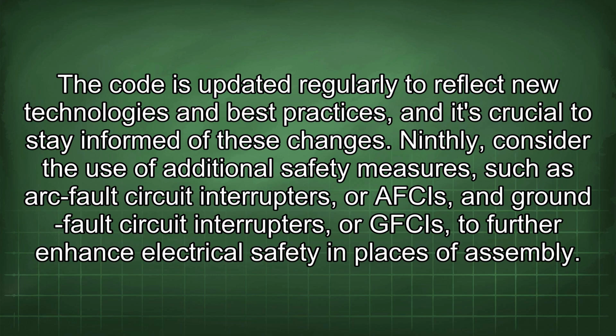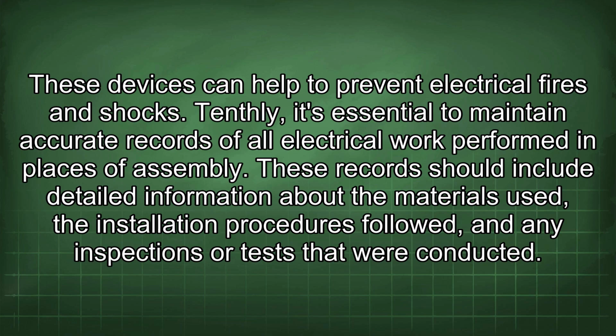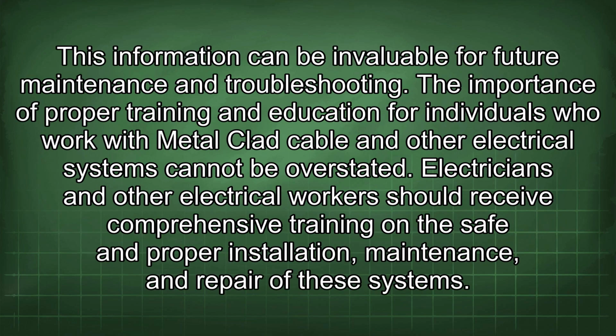changes. Ninthly, consider the use of additional safety measures such as arc fault circuit interrupters, or AFCIs, and ground fault circuit interrupters, or GFCIs, to further enhance electrical safety in places of assembly. These devices can help to prevent electrical fires and shocks. Tenthly, it's essential to maintain accurate records of all electrical work performed in places of assembly. These records should include detailed information about the materials used, the installation procedures followed, and any inspections or tests that were conducted. This information can be invaluable for future maintenance and troubleshooting.